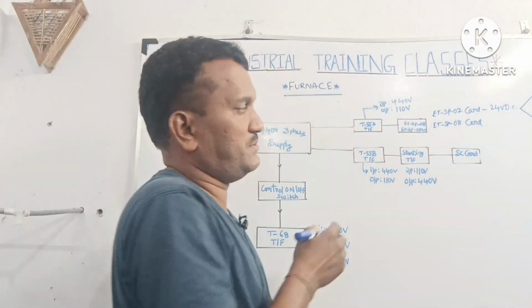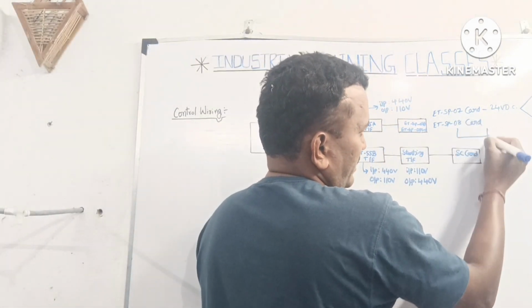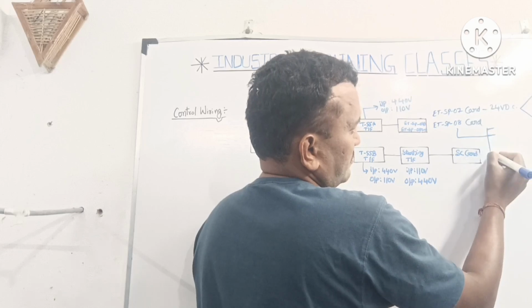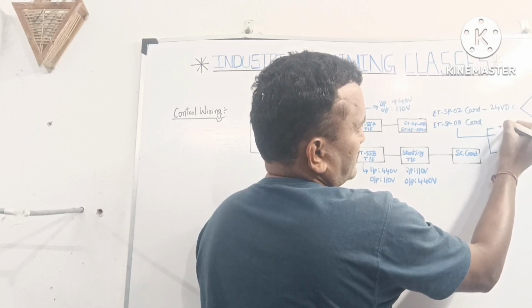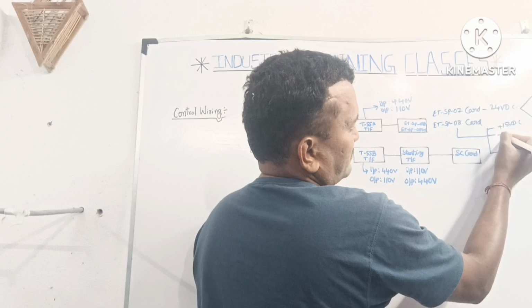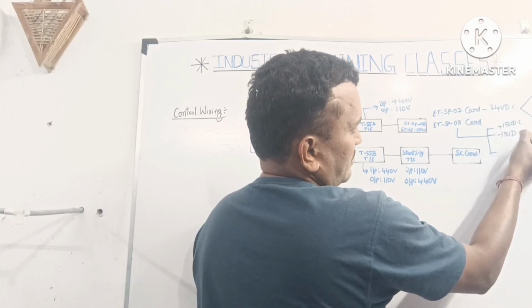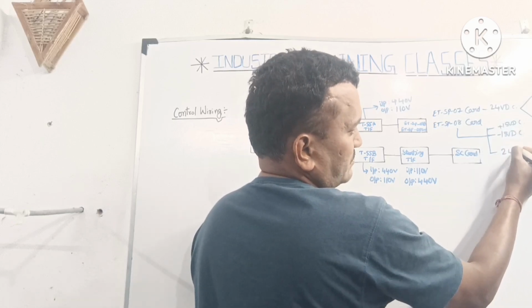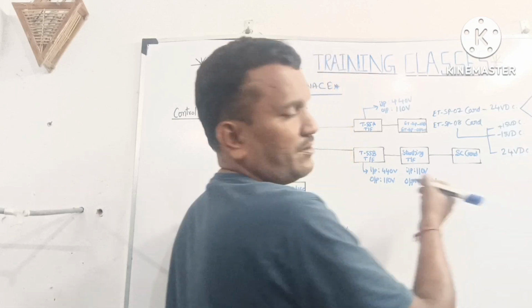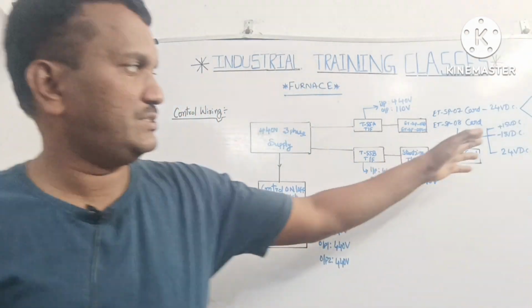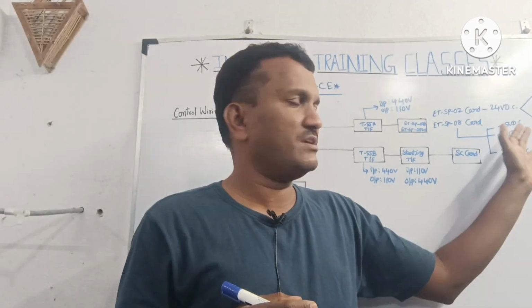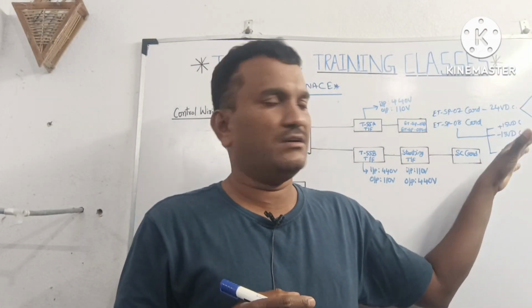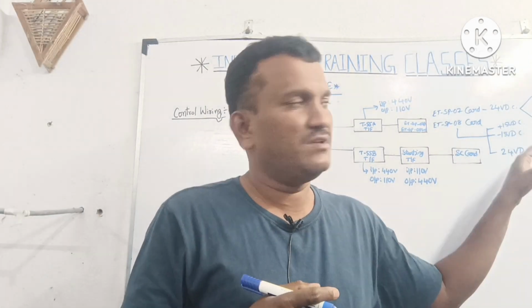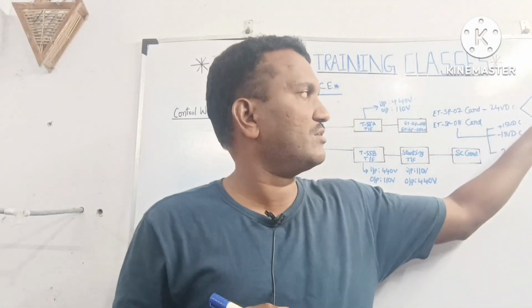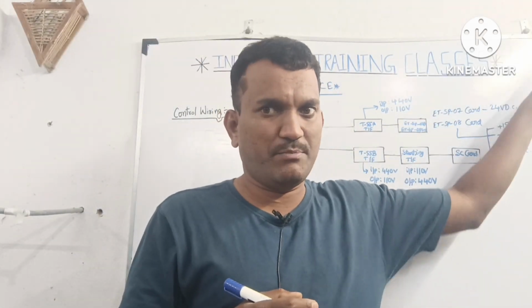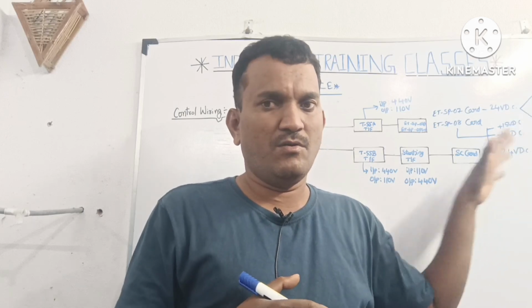The ETSP08 card gives 3 supplies: plus 15 volt DC, minus 15 volt DC, and 24 volt DC. This supply goes to the SL card, ITC card, and relay boards. Particularly the SP07 card goes to the converter-inverter section for pulses purpose.